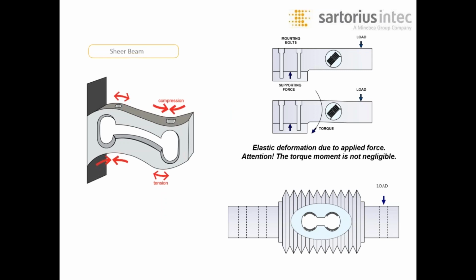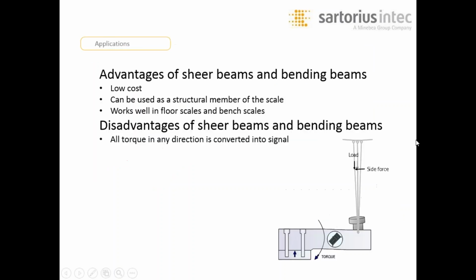Once again, the strain gauge is a device that measures electrical resistance changes in response to the proportion of strain or pressure or force applied to the device. The most common strain gauge is made up of very fine wire or foil set up in a grid pattern in such a way that there's a linear change in electrical resistance when strain is applied in one specific direction. Most commonly found with a base resistance of 120 ohms, 350 ohms, or 1,000 ohms. Each strain gauge has a different sensitivity to strain, which is expressed quantitatively as the gauge factor. The gauge factor is defined as the ratio of fractional change in electrical resistance to the fractional change in length. The typical gauge factor for metallic strain gauges is around 2.